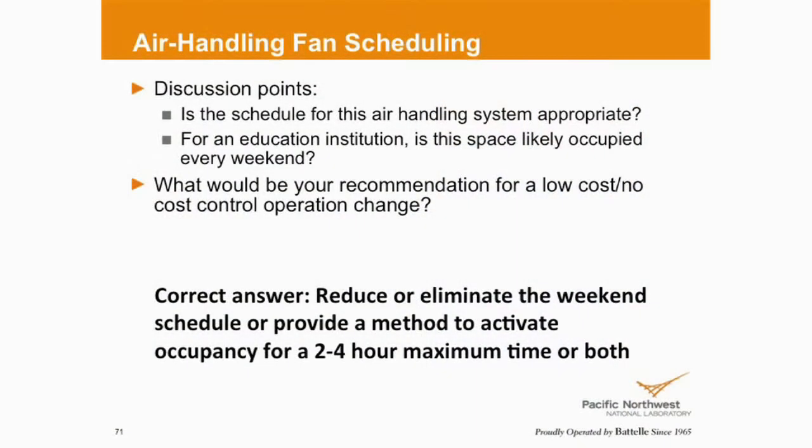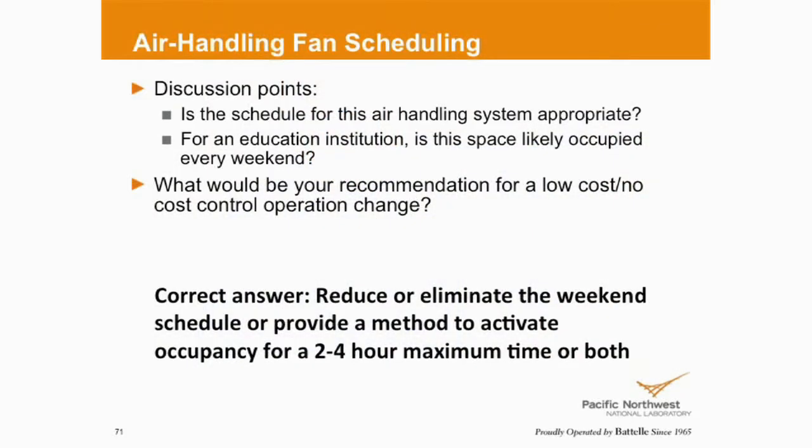So, is the schedule for this air handling system appropriate? Well, it's an educational institution. Is this space likely occupied every weekend? Well, not only that, but it's not occupied 24 hours. Yeah, there should be some setbacks somewhere. So that brings us to the last bullet. We've heard setbacks, limit the economizer.